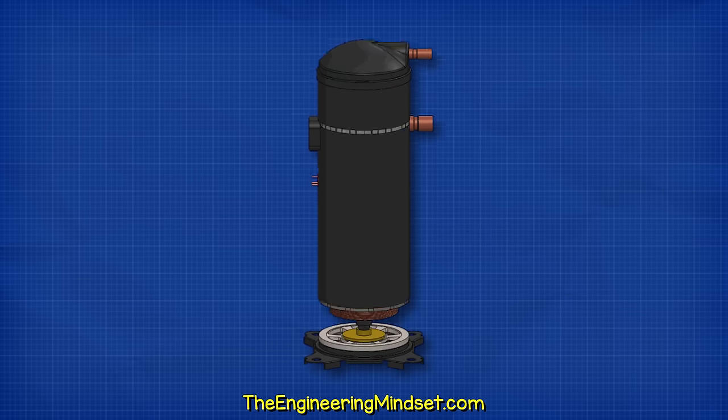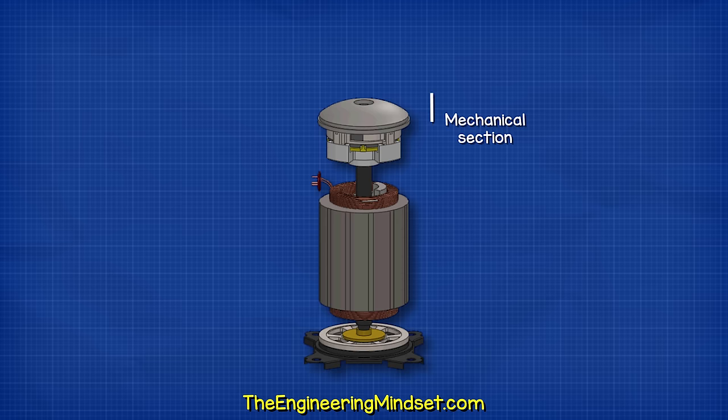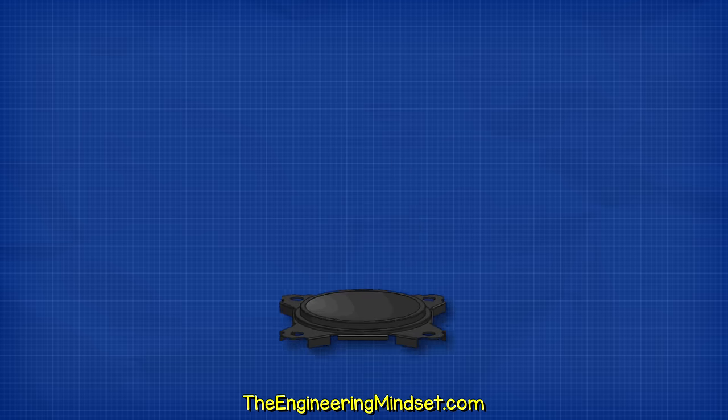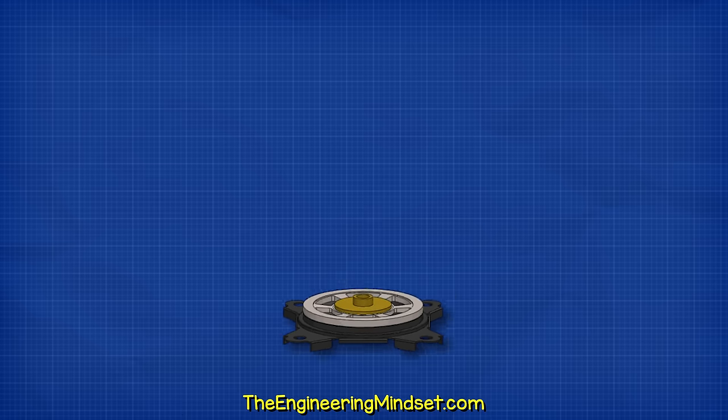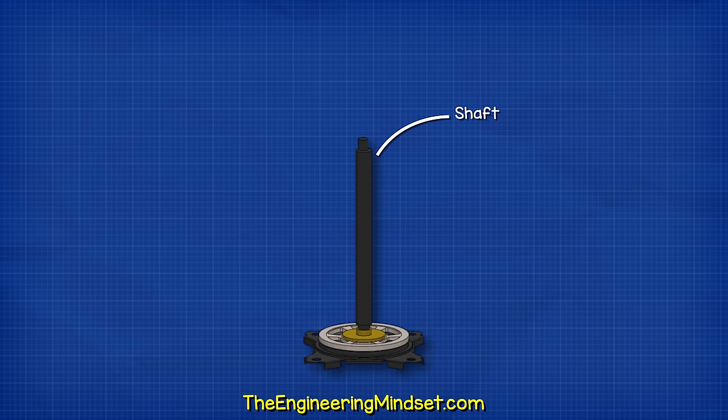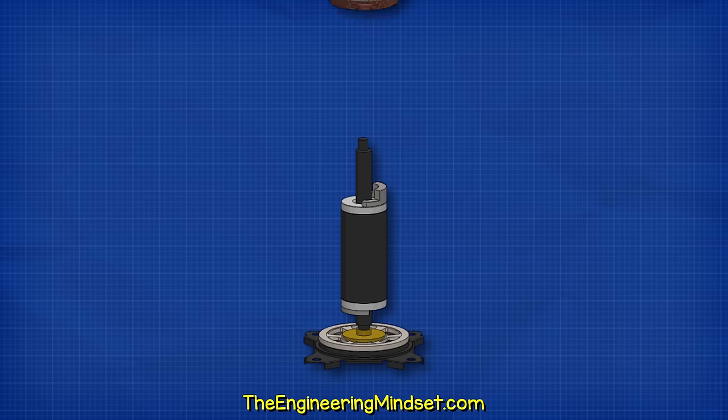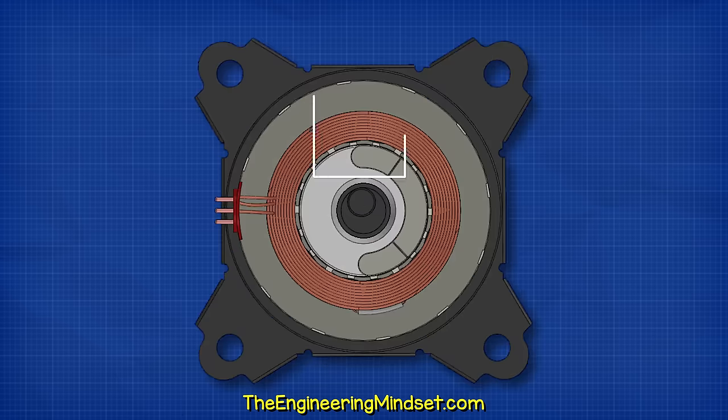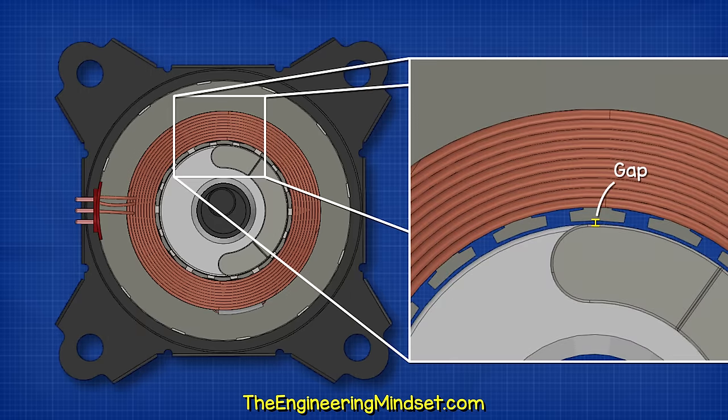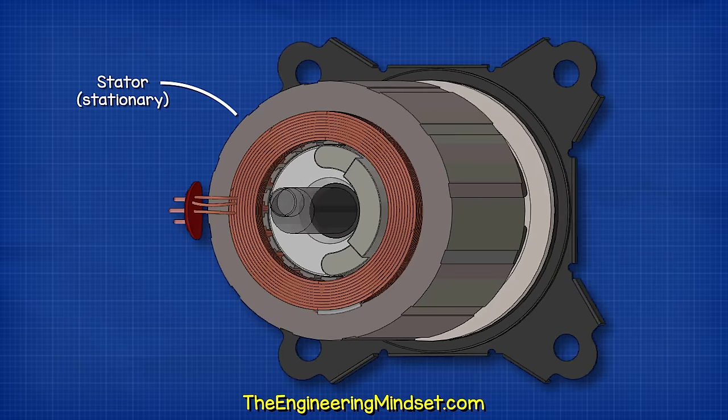When we remove the shell, we see there is a mechanical section and an electrical section. At the bottom, we usually find some type of support with a bearing built into this. The shaft will sit within this bearing and rises up through the compressor. Connected to the shaft is the rotor. Surrounding the rotor is the motor stator. There is a small gap between the stator and the rotor. The stator remains stationary, but the rotor rotates.